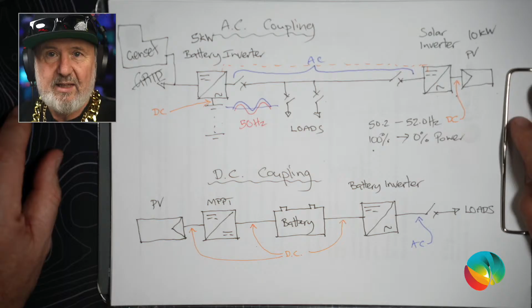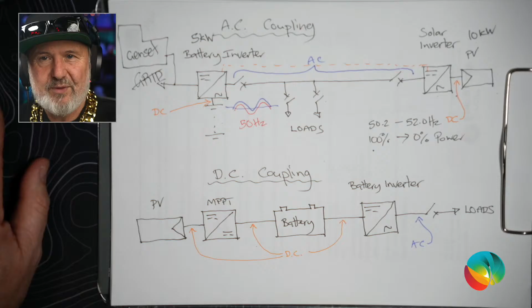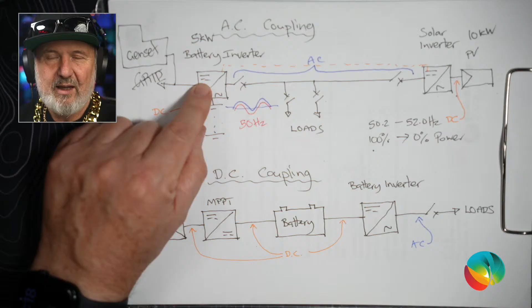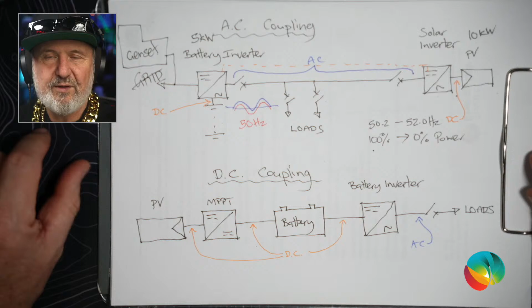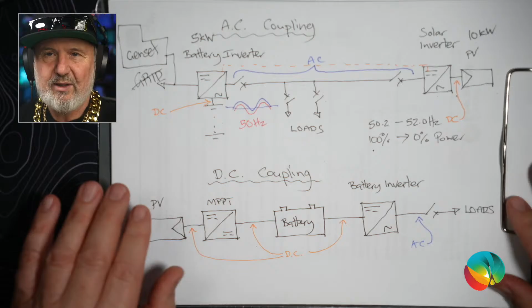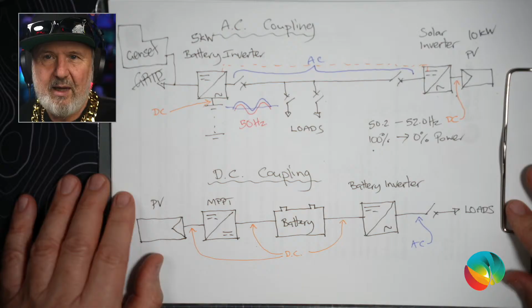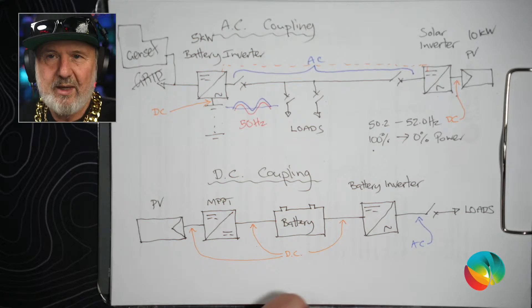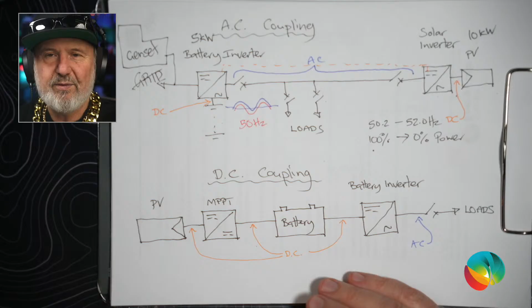2-to-1, not uncommon. And here at the Smart Energy Lab, we were doing 4-to-1 for a trial, and it pretty well worked. We did get a few little overshoots. What tends to happen if you don't get it right is the battery inverter can go into grid protection mode, basically. What it does is it raises the frequency very quick to 55 hertz, which kicks off every solar inverter. Comms ones, generically coupled ones, that it kicks them off and they instantly stop generating. And then about 90 seconds to 2 minutes later, they start ramping up again, typically over about 6 minutes. That's the default ramp rate to full power again. So you have this kind of on-off thing happening, which isn't really elegant.